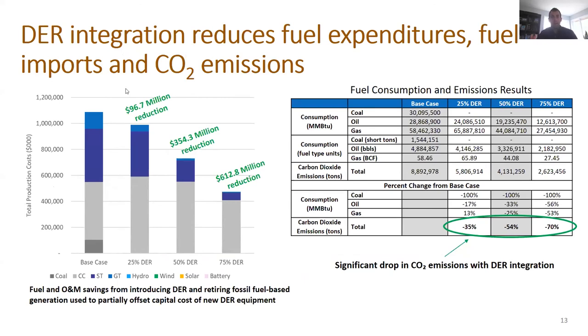And lastly, I touched on previously the carbon emission reductions. We also calculated the total production cost reductions. And so here, production cost is a combination of fuel costs, variable operations and maintenance costs, and startup and shutdown costs. This is an important metric because this is the avoided cost of the DER generation. So we're showing between $100 million and $600 million of avoided, essentially avoided fuel cost savings. Now, these are not net savings. This is the avoided fuel cost. Obviously, a portion of these fuel savings or all of it would have to go to offset the cost of the new DER. And so that's something Anna will touch on later in the presentation.